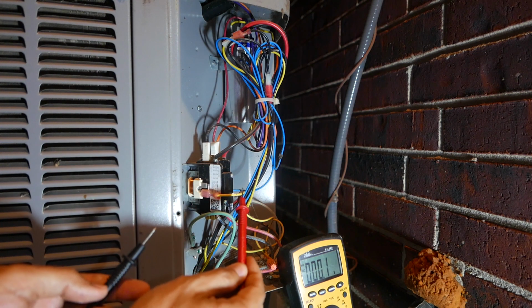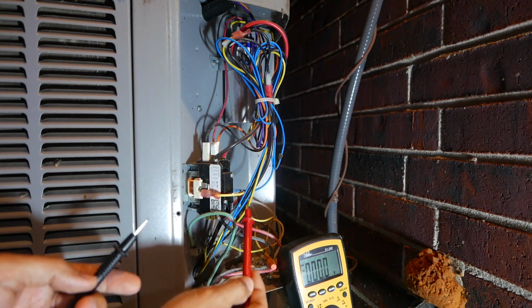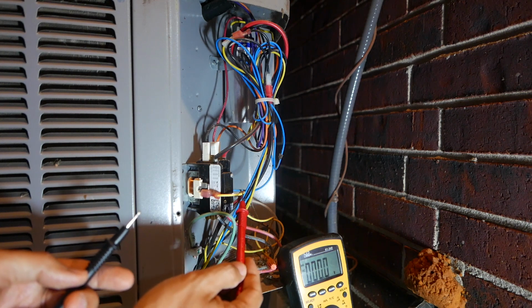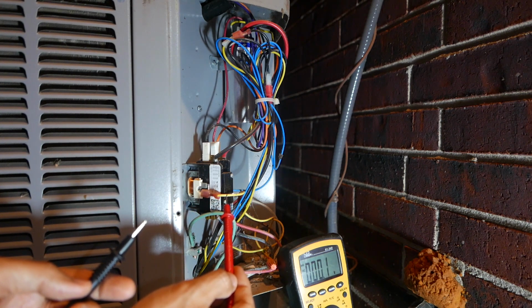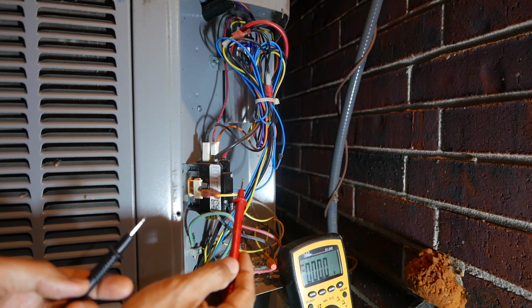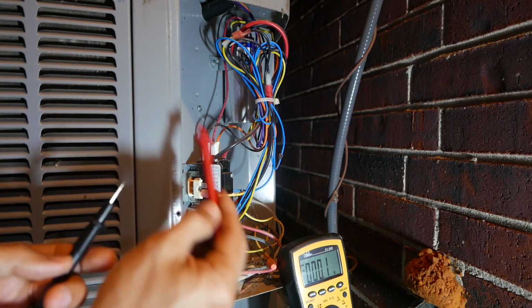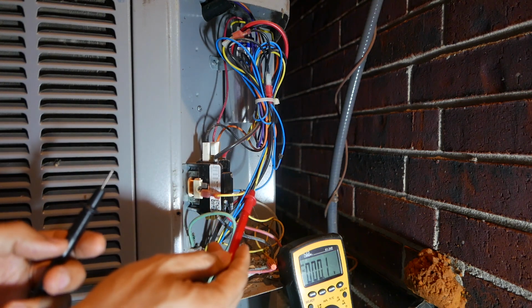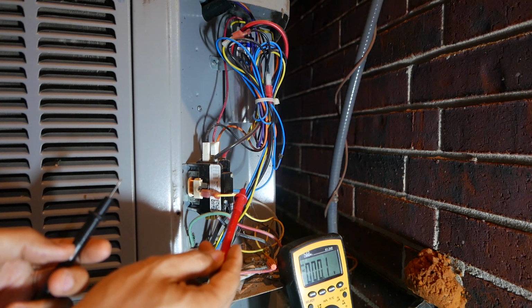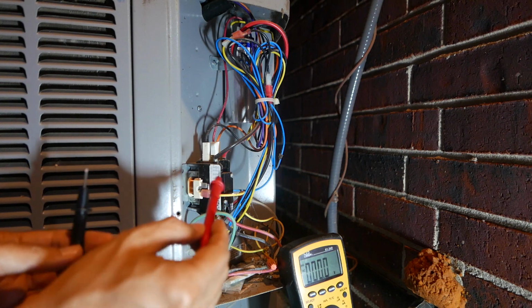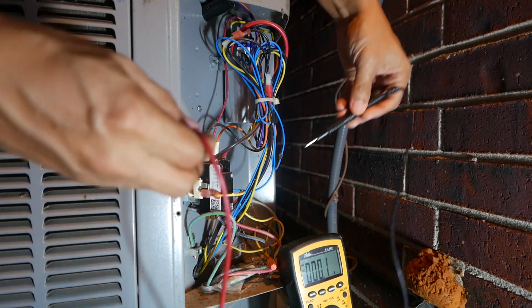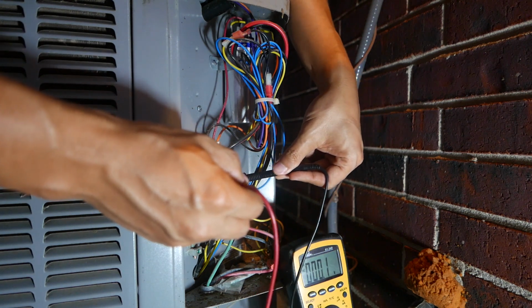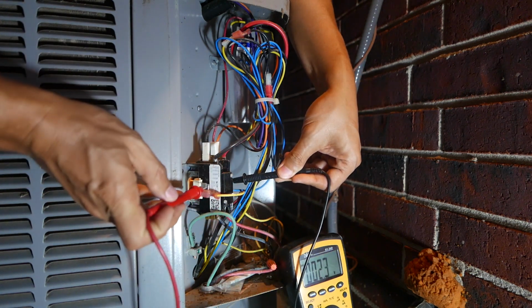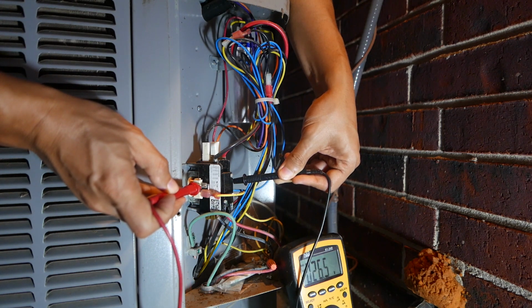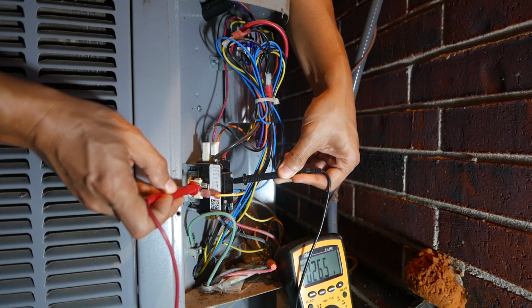Alright, so do you see this yellow lead and this blue lead right there, these two right here? So these two go all the way to the thermostat and air handling unit, and when this condensing unit needs to come on, the 24 volt VAC signal should send out over here. So let's check and see if I have 26 volts VAC, because if I don't, then it's inside, but if I do, then there's something wrong out here. Oh, so look right there. I do have 26 volts VAC.